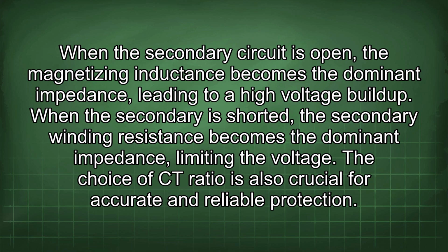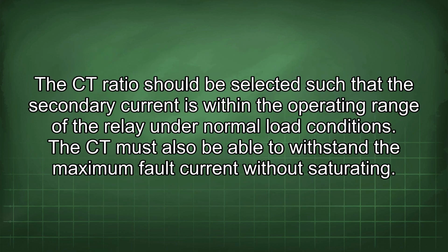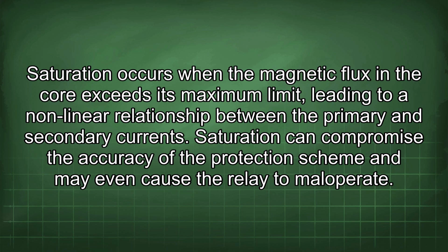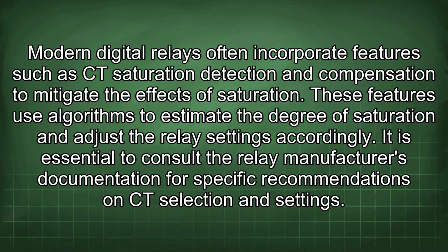The choice of CT ratio is also crucial for accurate and reliable protection. The CT ratio should be selected such that the secondary current is within the operating range of the relay under normal load conditions. The CT must also be able to withstand the maximum fault current without saturating. Saturation occurs when the magnetic flux in the core exceeds its maximum limit, leading to a nonlinear relationship between the primary and secondary currents. Saturation can compromise the accuracy of the protection scheme and may even cause the relay to maloperate. Modern digital relays often incorporate features such as CT saturation detection and compensation to mitigate the effects of saturation. These features use algorithms to estimate the degree of saturation and adjust the relay settings accordingly. It is essential to consult the relay manufacturer's documentation for specific recommendations on CT selection and settings.